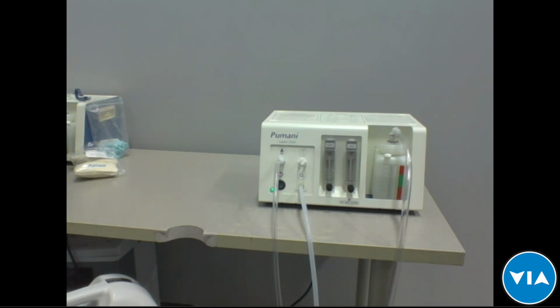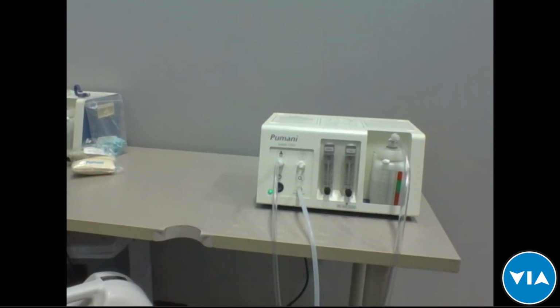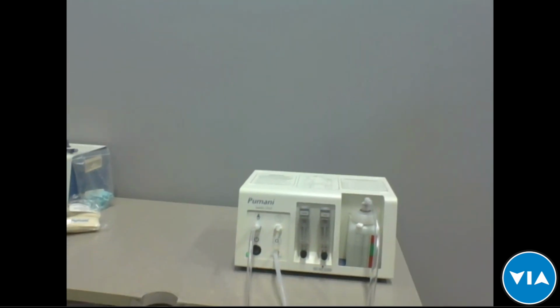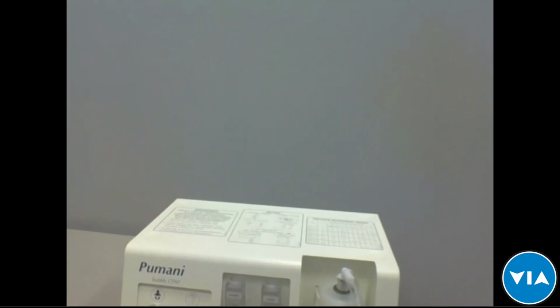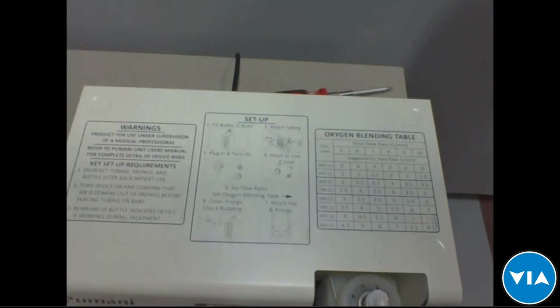So now that you have the flow meters open, the concentrator or tank connected, you can select your FiO2. So you're basically selecting the settings you want to give that specific patient. So room air, the normal air we breathe, is 21% oxygen. And to get to pure oxygen, you go all the way up to about 100% oxygen. And you need to find in between there the setting that's appropriate for the baby in order to get their saturations up to the recommended amount. And, you know, oxygen is a drug, and so it's dangerous and it can cause harm if too much is given to premature babies, and that's why the use of a pulse oximeter is always recommended.